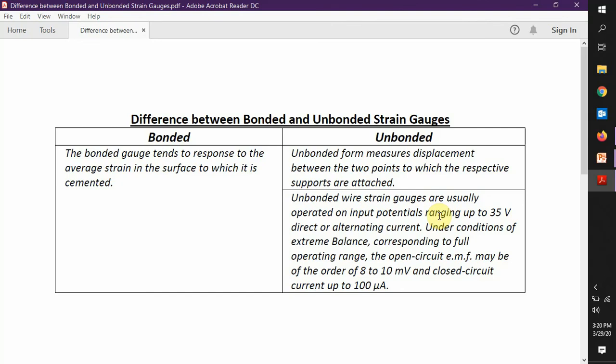Unbonded wire strain gauges are usually operated on input potential ranging up to 35 volts, direct or alternating current. Under conditions of extreme imbalance corresponding to full operating range, the open circuit EMF may be of the order of 8 to 10 millivolts and the closed circuit current up to 100 microamps.